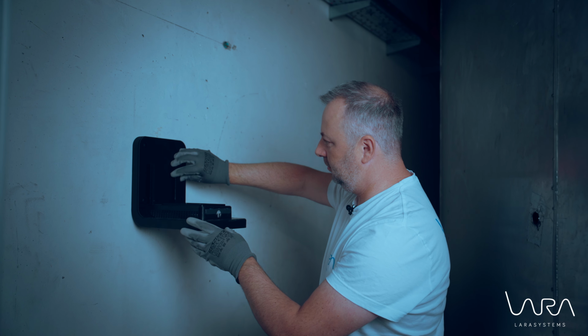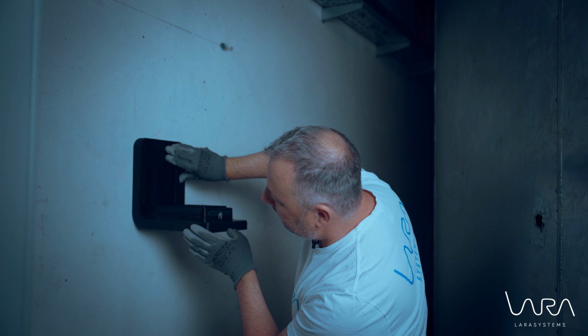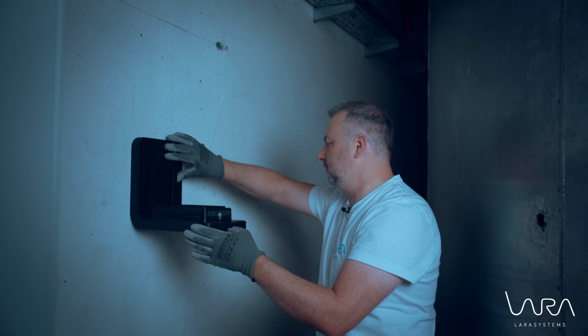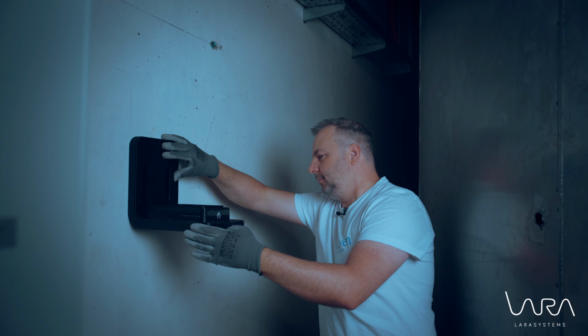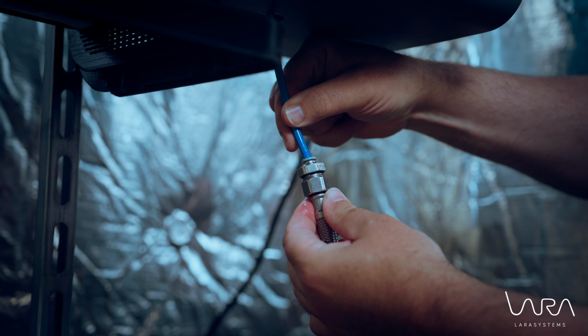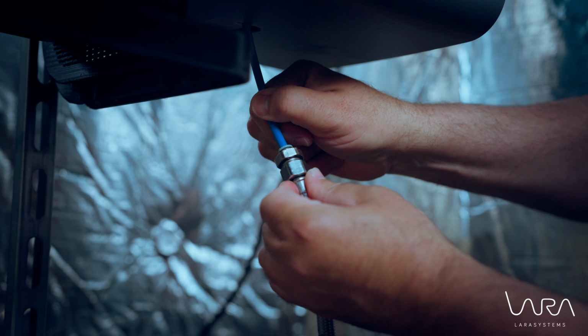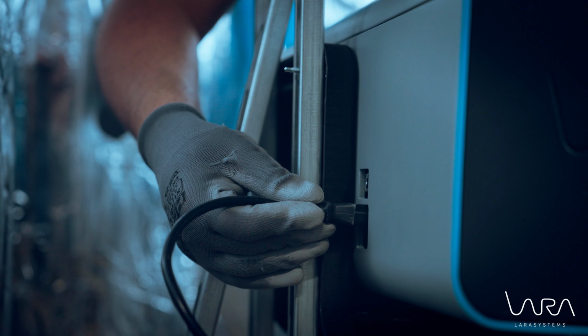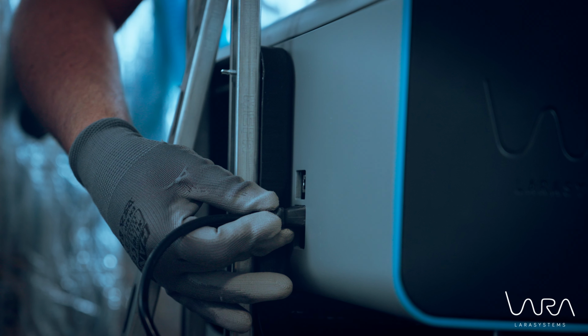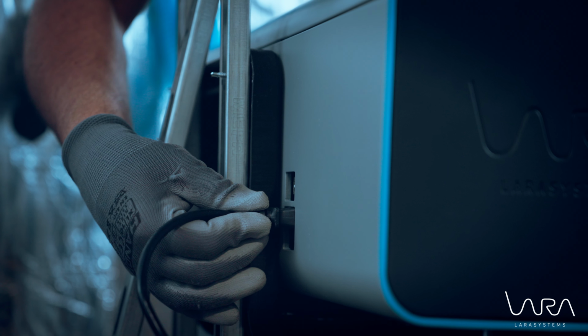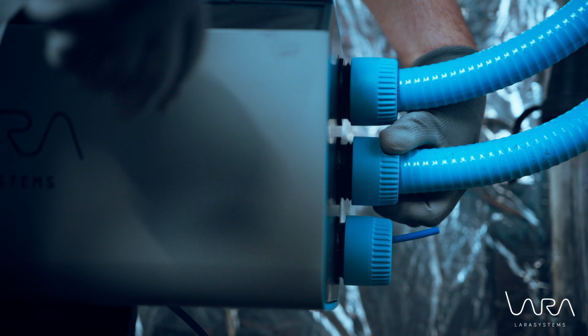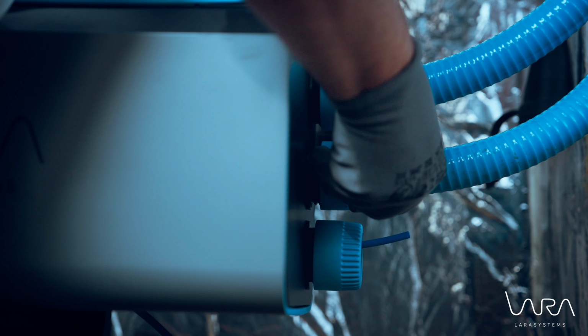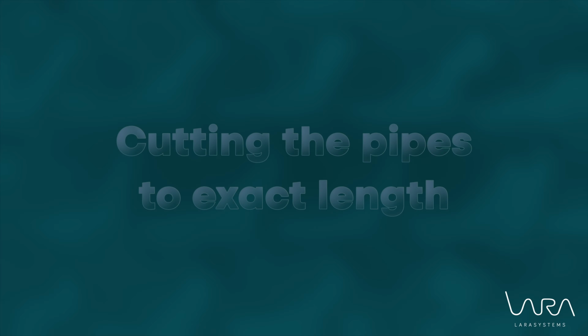In the case of wall mounting, the load-bearing capacity of the wall and the accessibility of the device must be checked. Regardless of the placement method, the device must be stable, accessible, and the pipe, water, and electrical connections must not be under tension. After successfully mounting the device and the supply heads, the third step is to cut the pipe lengths to size and then connect them.